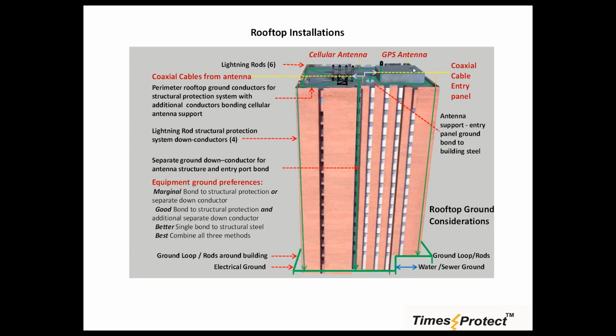If you are dealing with high-rise buildings, they are going to be populated not only with a structural lightning protection system, a bunch of spikes hanging around which is tied to the structural steel of the building, or is going to have vertical radials coming down. If this is a brick building, for example, and you have a penthouse, you might have a higher tower, you might have a lot of point-to-point, point-to-multipoint antennas on small masts sitting back there, tied directly to the overall structural lightning protection system.